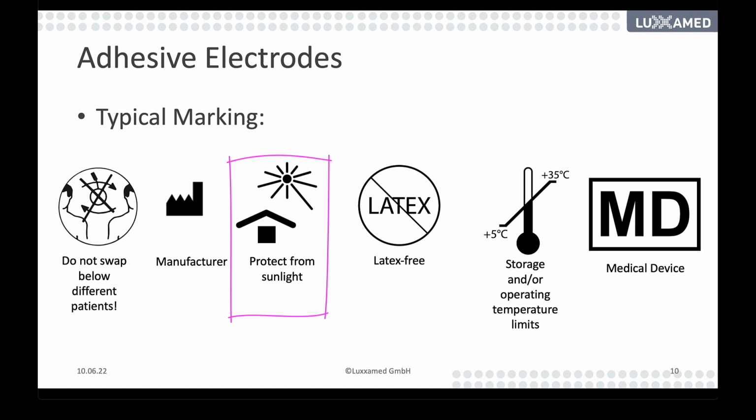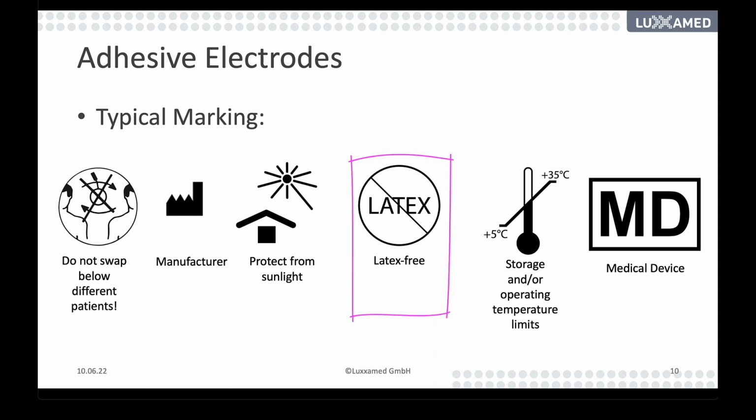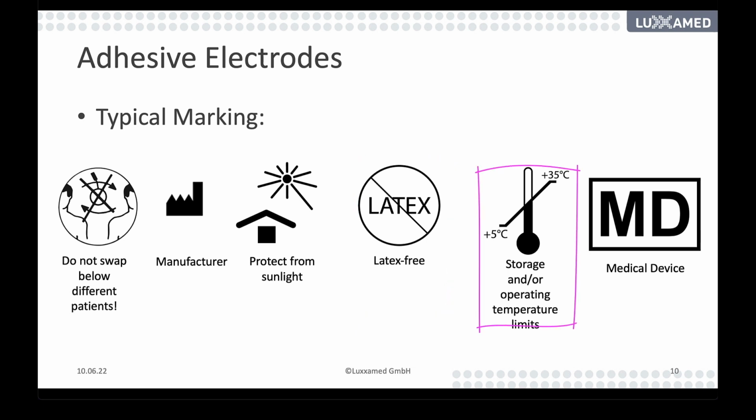These electrodes are very sensitive to sunlight, because the adhesive part of the electrodes is like a gel, and if you dry it out by sunlight, they won't be usable anymore. Then, of course, adhesive electrodes have to be latex free because of allergic reactions. It's also important to know how to store them, and the operating temperature limits can be very important for the electrodes.